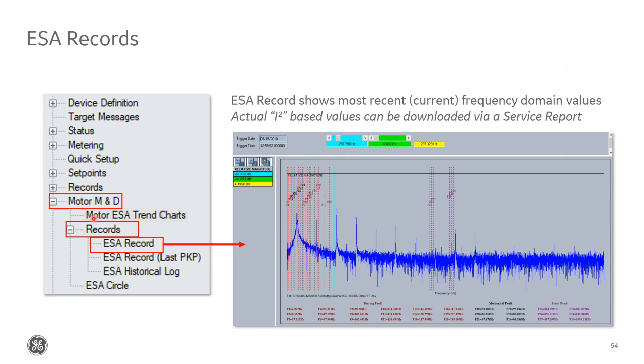In the records menu, we have several different options. Here we're showing the FFT option. This is where you can see what fault frequencies are flagged. You can see them all labeled down here. We show you the fundamental and then the complete frequency spectrum that we see from the current stator sample. What we're looking for in here is any spikes at those specific fault frequencies. This is all recorded in the background, but we just give this to you visually so you can take a look at this if you'd like.